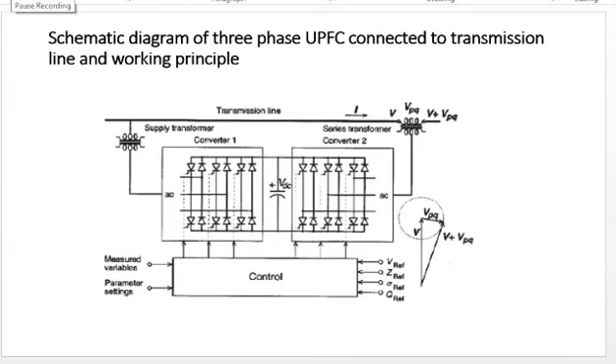Converter one supplies or absorbs the real power demanded by converter two at the common DC link to support the real power exchange resulting from the series voltage injection. This DC link power demand of voltage source converter two is converted back to AC by converter one and coupled to the transmission line bus through the shunt-connected transformer.